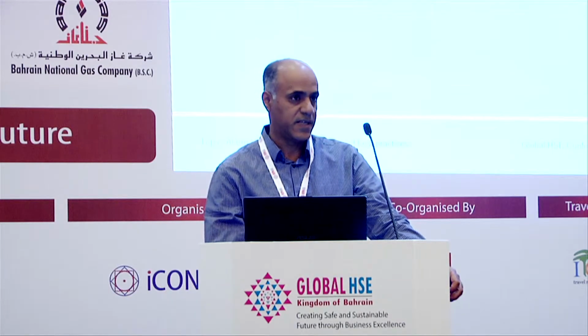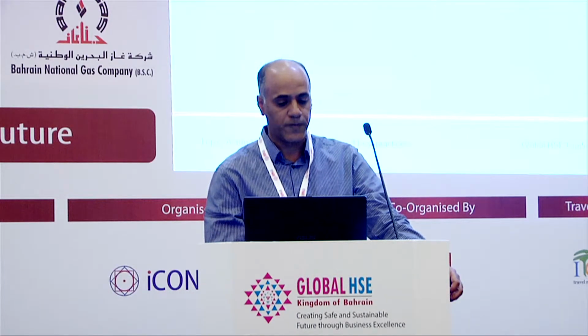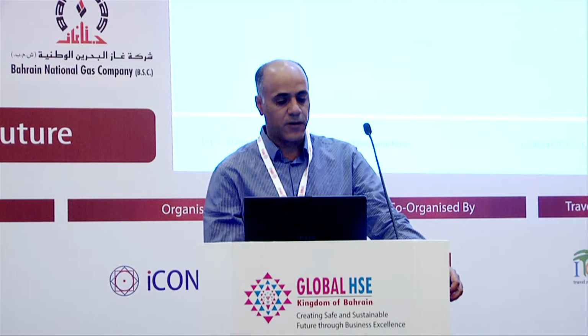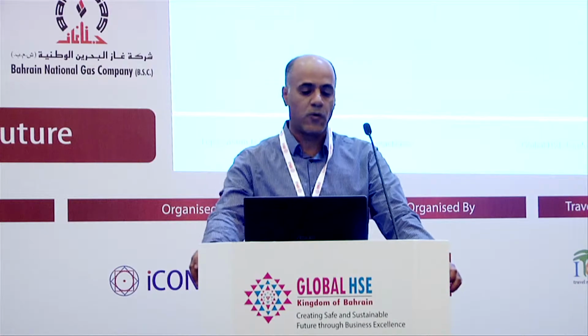So what is an alarm in the first place? As per the standard ISA 18.2, it defines an alarm as an audible and visible means of indicating to the operator an equipment malfunction, process deviation, or abnormal condition requiring timely response.